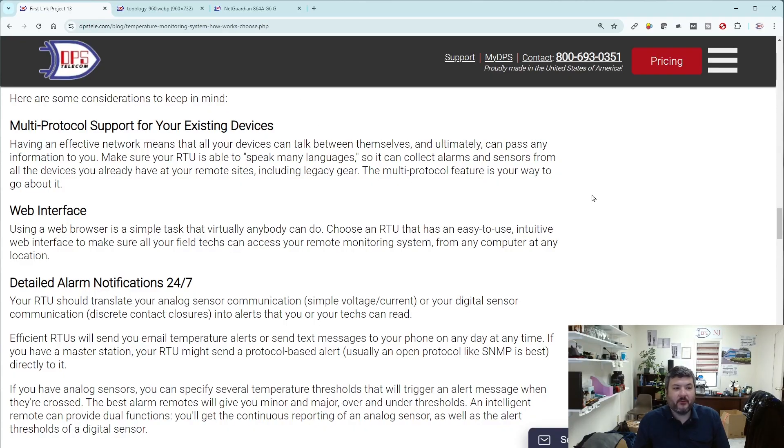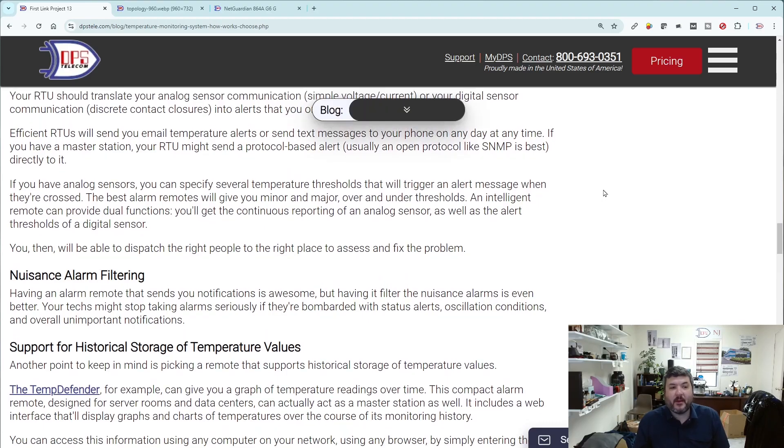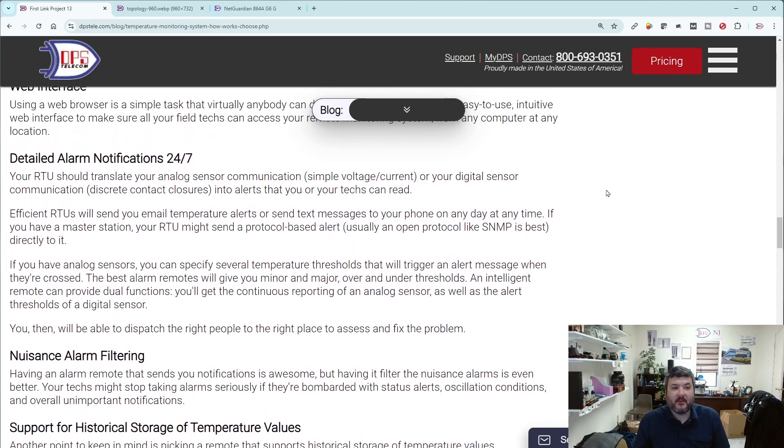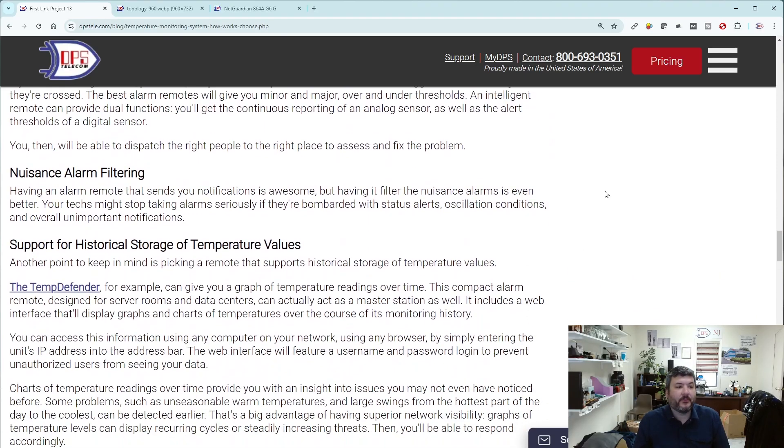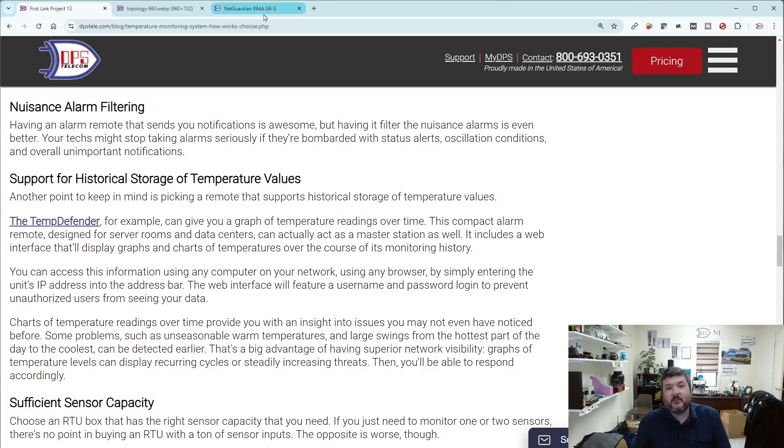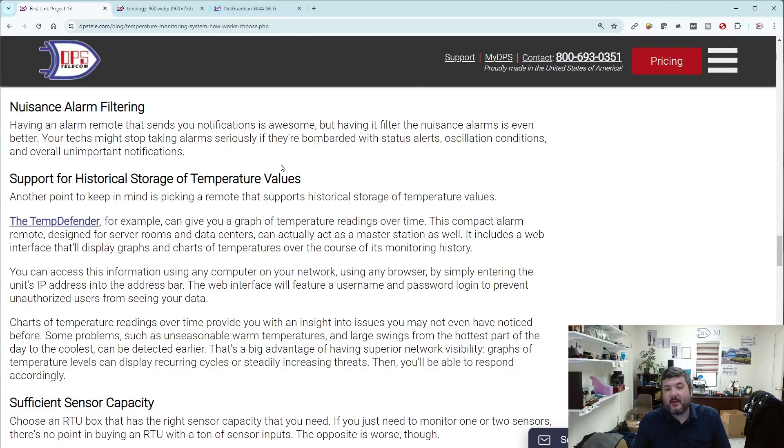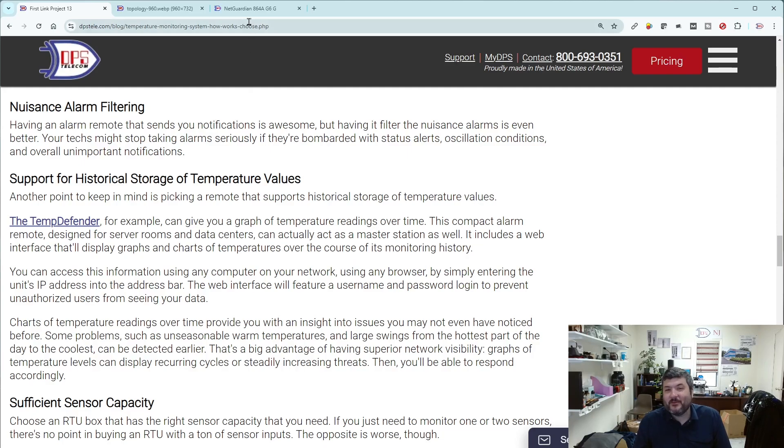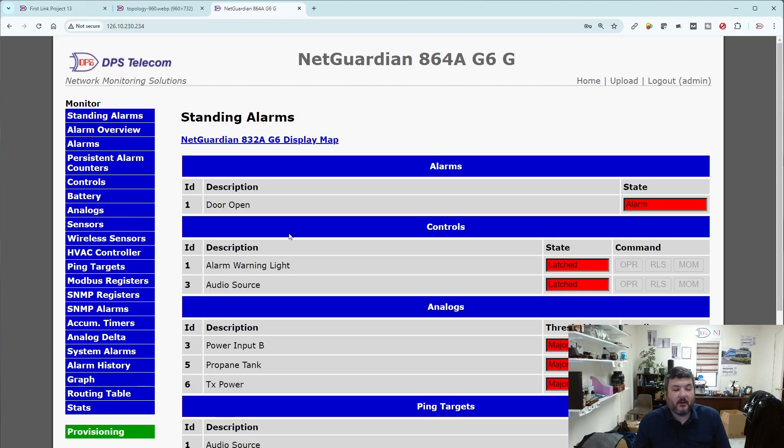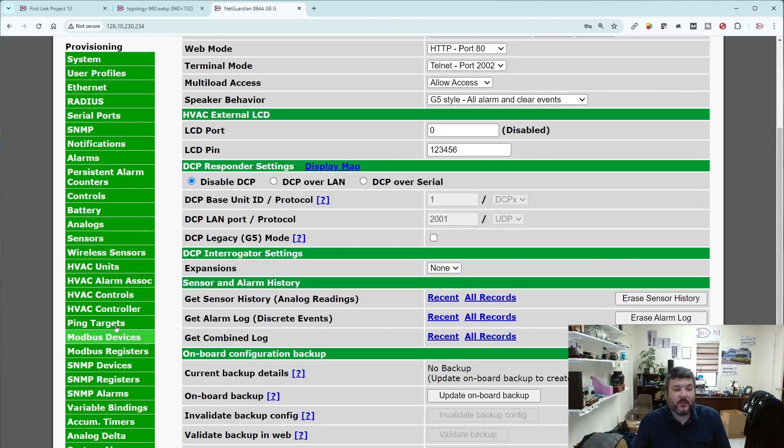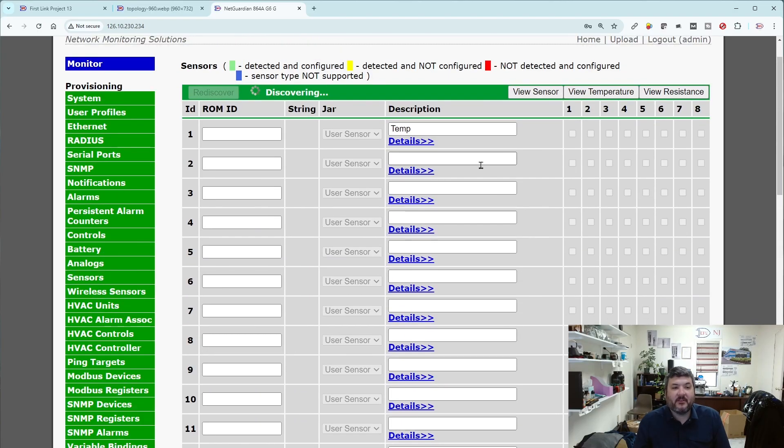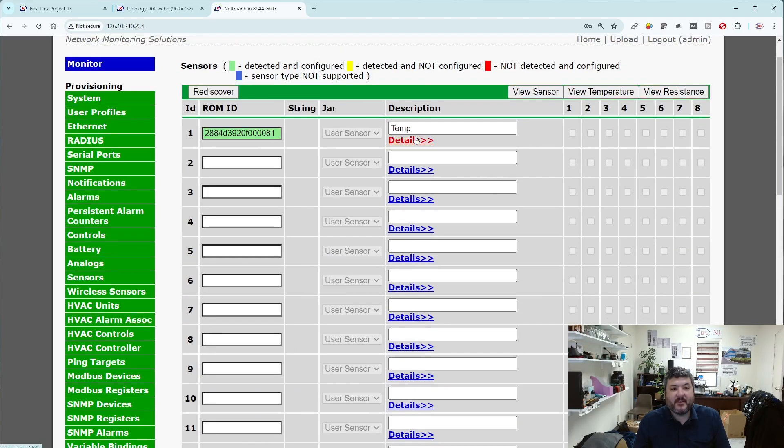At an RTU level, we want nuisance alarm filtering. This is an ability to say 'I don't want to get certain alarms because they're annoyances. They do not need to be responded to.' Examples of this in temperature might be 'I have my threshold set too aggressively. The thing sends alerts when it doesn't need to yet.' In the RTU context, if I go to my provisioning, this is where I configure everything rather than just use it. So this is my initial setup. If I go to sensors and I have that temp sensor, I could change my thresholds. I could say 85 is not so bad, let's make it 89 degrees.